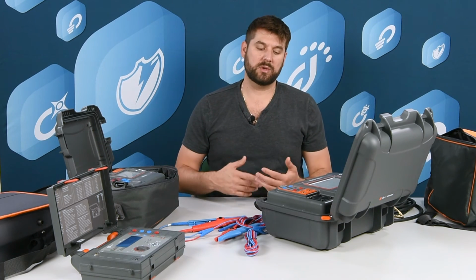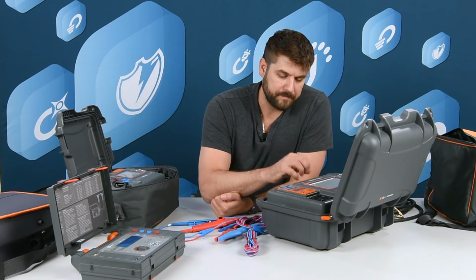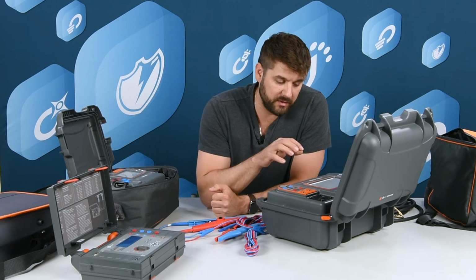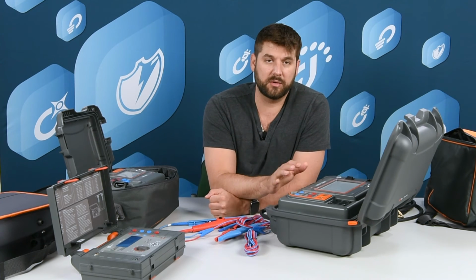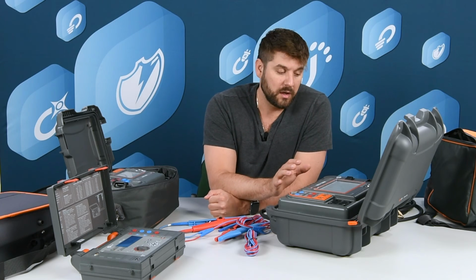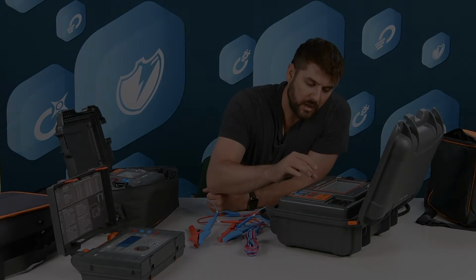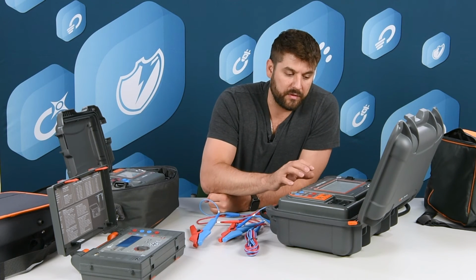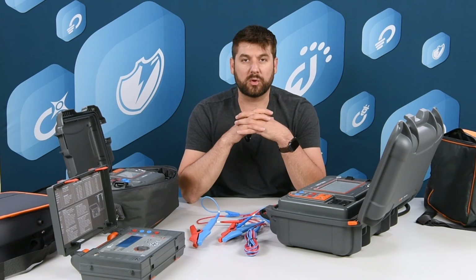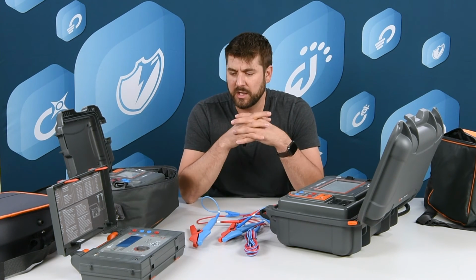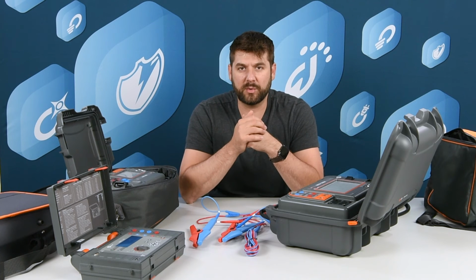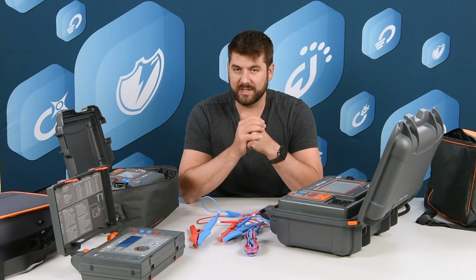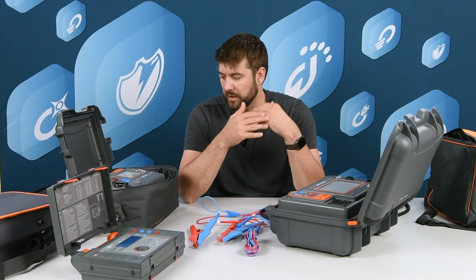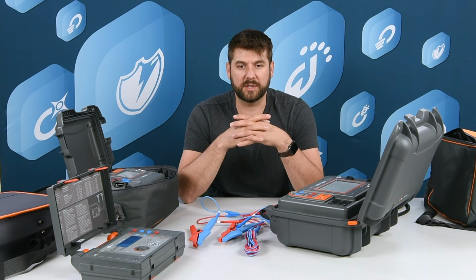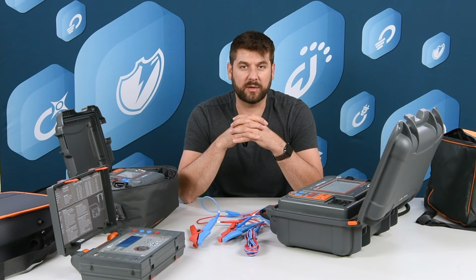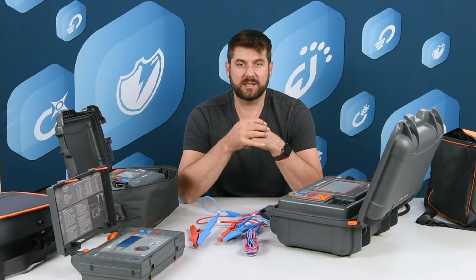So you can add to the memory, you can store your measurements. Of course, these are all battery powered. Even here, these high current MMRs are still powered by the battery. These have also been equipped with what we call core demagnetization. So if you're measuring a coil, a winding, a generator, a motor, even a CT, when you push DC through this test object, you're going to build up a magnetic field, which is going to have to be demagnetized afterwards.